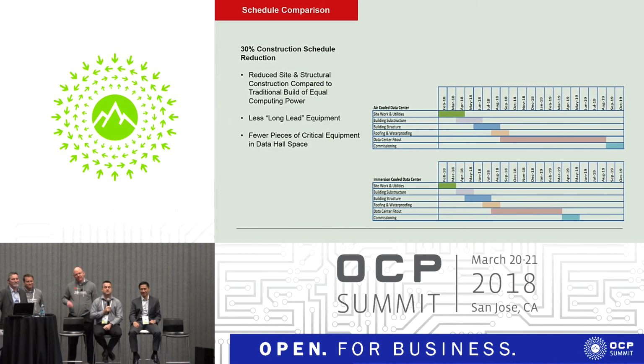Yes, sir, how often do you have to recycle the liquid? One year? Yeah, the fluorochemical fluids used here have, I hate to say infinite, but an indefinite service life. We do scrub the fluid in situ to remove contaminants and keep it clean, but that's not because of any degradation of the fluid itself - it's just because of contaminants it picks up from the electronics. So you can expect an indefinite service life, similar to a refrigerant in an automotive or residential AC system - you typically don't have to change that out.